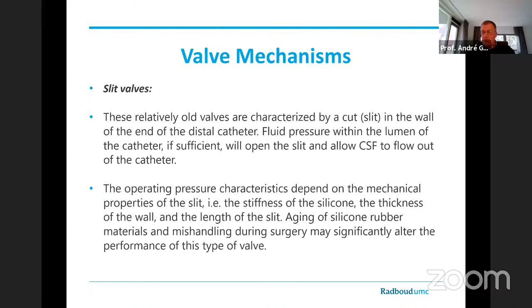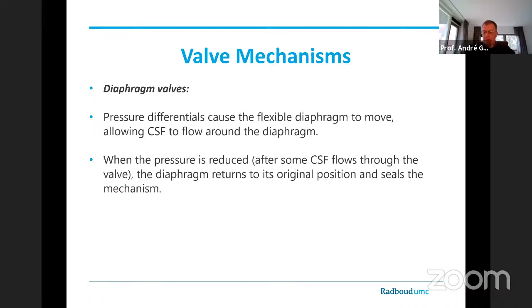Diaphragm valves are very common. It's simply by the differential pressure between proximal and distal that a flexible membrane will move. So if the pressure is high enough, it will push this flexible membrane up, allowing CSF to flow through. And when the pressure is lower again, the membrane comes back to its old position and closes off the shunt, the valve, until, of course, the pressure increases again.